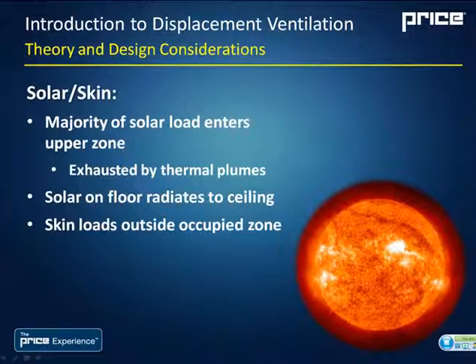The final component of the loads are the solar and skin loads. So the majority of the solar load is actually entering the upper zone, and that's going to be exhausted through thermal plumes. And any solar that happens to fall on the floor is going to warm the floor, of course, but that's going to then radiate to the ceiling, which is, again, outside the occupied zone. So the majority of your heat transfer with solar loads is really falling outside the occupied zone. And the final point, skin loads are outside the occupied zone because we're typically not occupying that 1-foot zone directly beside the wall or the window.